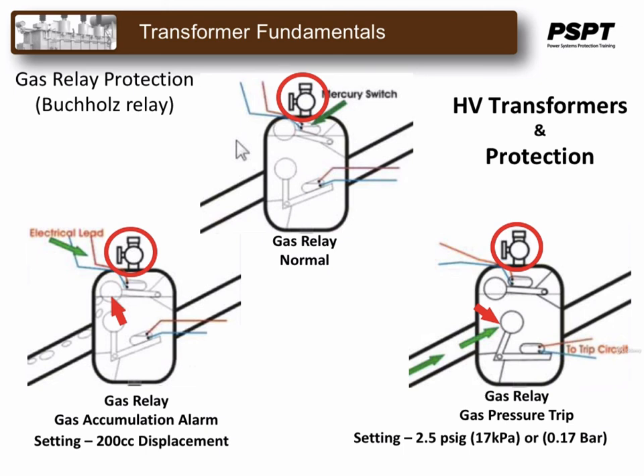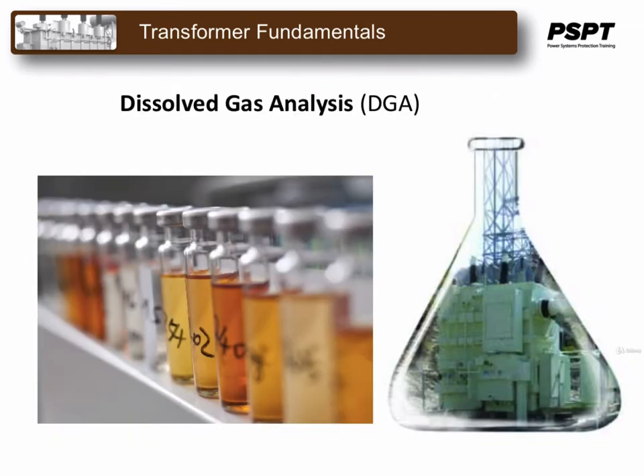Flammable gases found in the relay indicate some internal fault such as overheating or arcing, whereas air found in the relay may only indicate low oil level or a leak. Dissolved gas analysis, or DGA, is the study of dissolved gases in transformer oil. Insulating materials within transformers and electrical equipment break down to liberate gases within the unit. The distribution of these gases can be related to the type of electrical fault, and the rate of gas generation can indicate the severity of the fault.